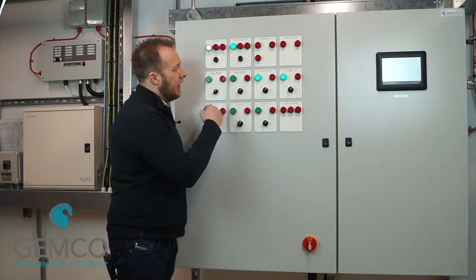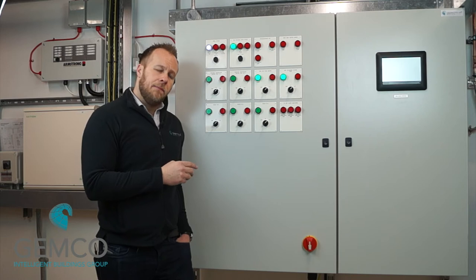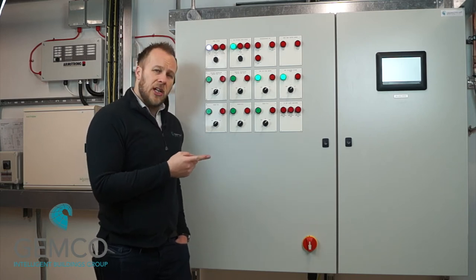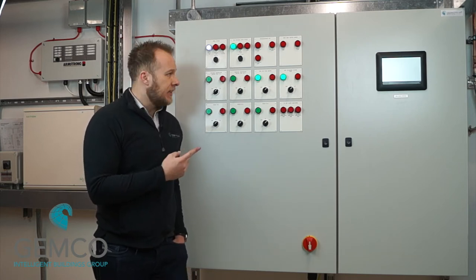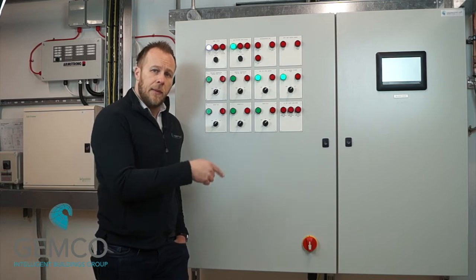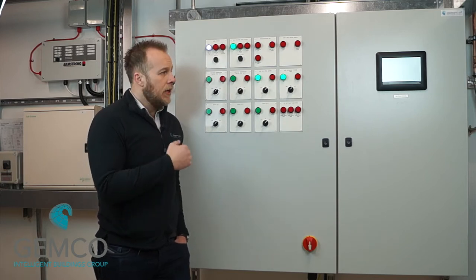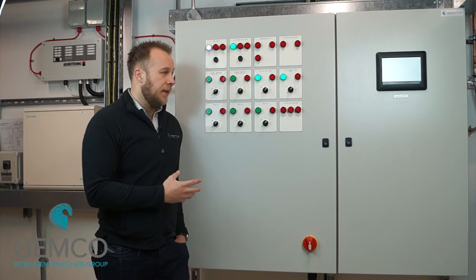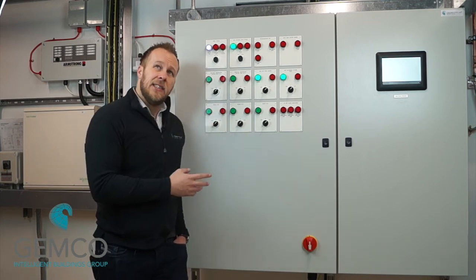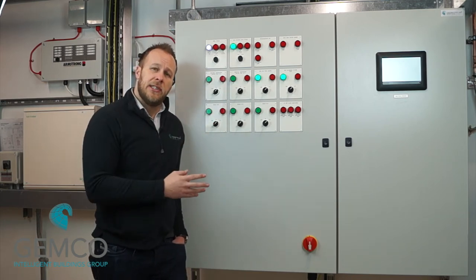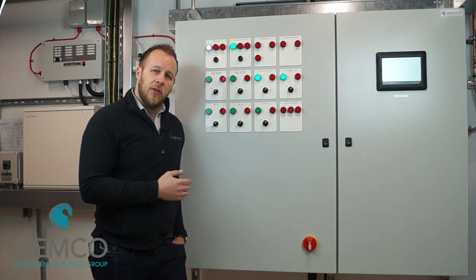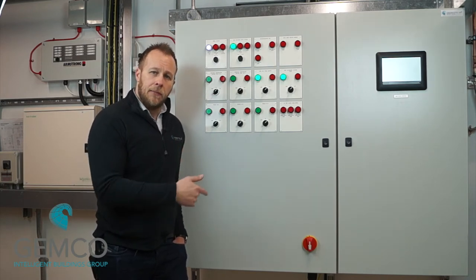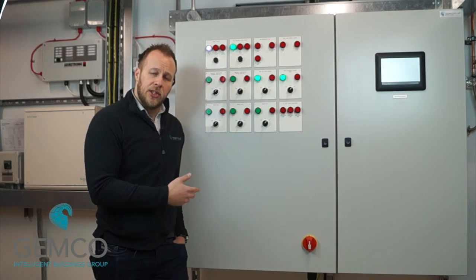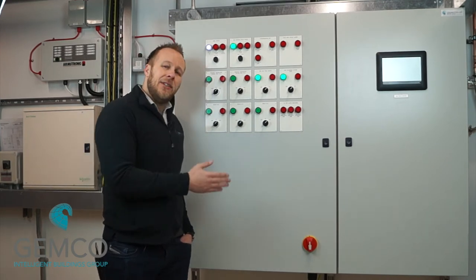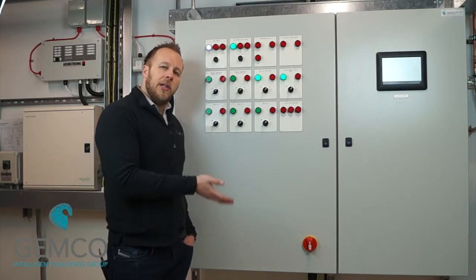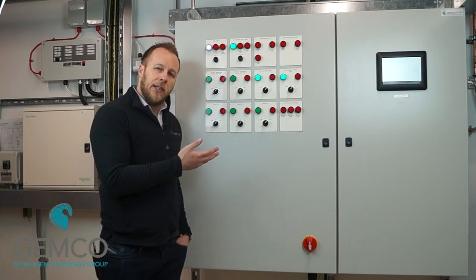Now, there's three levels of frost protection. If the outside air drops below 0 degrees, we run the pumps and we circulate the pumps to stop a frost in the pipework. The second stage is we monitor the immersion sensors, all the temperature sensors in here, and if that drops below 12 degrees, we run the pumps as well, just to circulate the water. And if that continues to drop, we then bring on the boilers just to elevate the temperature above 21 degrees.